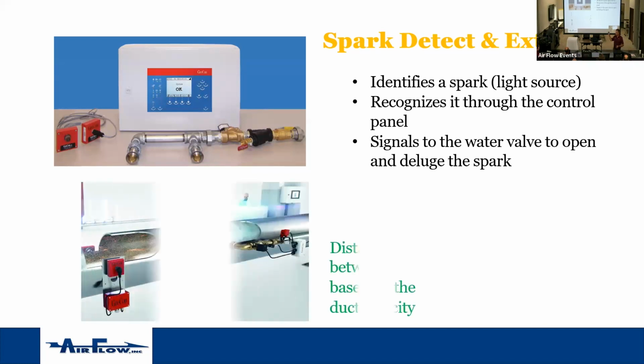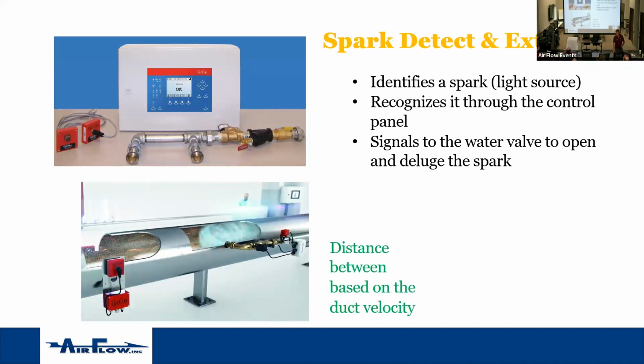The other one is a spark detect and extinguish. What this does is it takes a set of eyes located in your duct that sense a spark coming through. When it senses that spark coming through, it's going to send a signal to the control panel. The control panel is going to recognize that it saw a spark. It's going to send a signal to your deluge valve, and your valve itself is going to open, and it's going to spray mist in that duct to extinguish that spark. And then it's going to shut itself off.